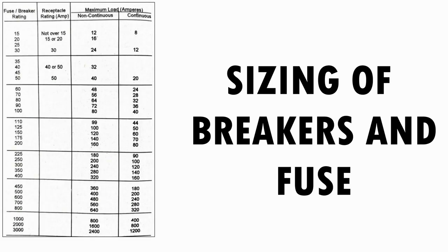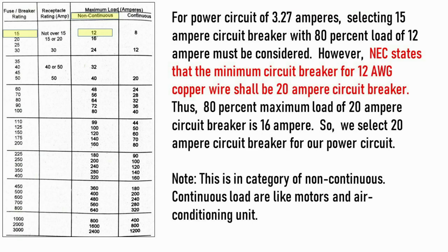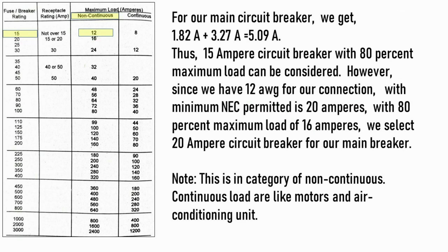For selection of circuit breakers or fuses for each circuit: for the lighting circuit with 80% maximum load, a 15-ampere circuit breaker can be selected — it will be safe for 12 amperes against 1.82 amperes. For the power circuit of 3.27 amperes, selecting a 15-ampere circuit breaker with 80% load of 12 amperes must be considered. However, NEC states that the minimum circuit breaker for 12 AWG copper wire shall be a 20-ampere circuit breaker. Thus, 80% maximum load of the 20-ampere circuit breaker is 16 amperes, so we select a 20-ampere circuit breaker for our power circuit.